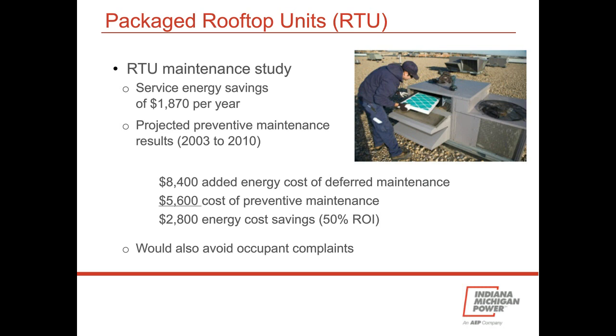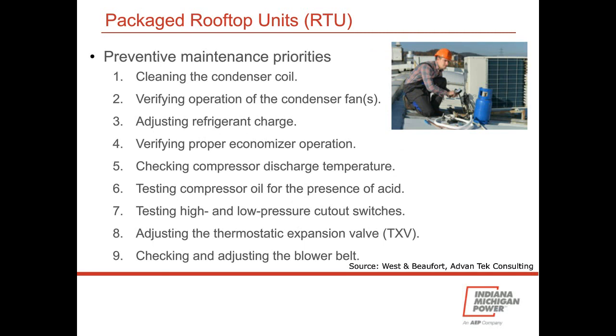And obviously you would avoid occupant complaints as well, which sometimes is the primary interest of a lot of facility managers. So, a good feel for the significant impact of poor maintenance on performance. So what can you do in terms of preventive maintenance priorities? Well, here's a minimum of at least 9 things. Clean the condenser coils, make sure the fan's working, get the right refrigerant charge, verify proper economizer operation.